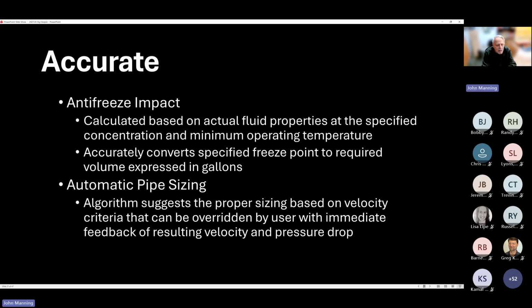Antifreeze. We spent a lot of time developing the equations necessary that calculate the fluid properties at the lowest operating temperature that's being specified in your design, the type of antifreeze, and the freeze point that you're specifying. And from that, we translate that into how much antifreeze is actually required, expressed in volume, not weight, which is often used when analyzing antifreeze.